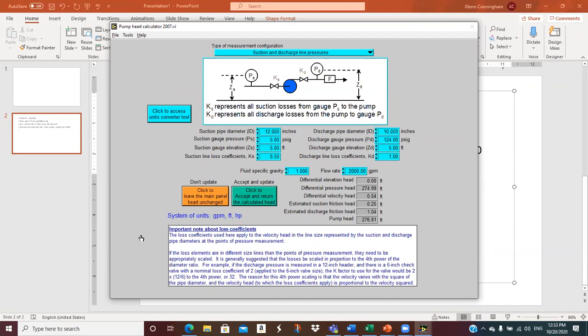And we actually have two different geometries that we can work from. This is one where you have a suction gauge and a discharge gauge. This K sub S would be some components. It could be a valve, a shut-off valve that's wide open, a strainer, just any piping component that's in there. That's the K sub S, the summation of the loss coefficients. It could be some elbows. The pipe could bend from the gauge to where it actually gets into the pump. So that accounts for pressure losses between the gauge and the actual pump itself.